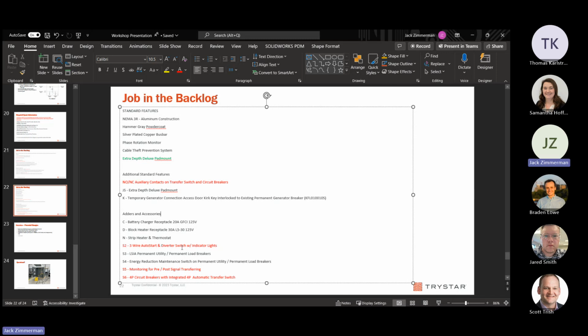So I don't know too much about this thing, but one thing I do know is that we have on the ATC controller remote auto start functionality coming off of 22 and 23. I have it programmed. This is a normally closed contact, so when the controller shuts down, it starts up the generator by design, because if you lose all power, you want your generator to come online. That's the concept.